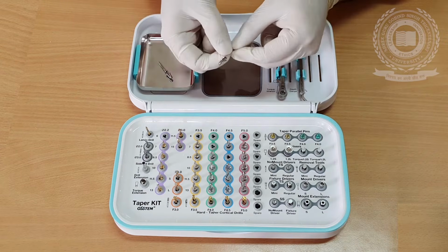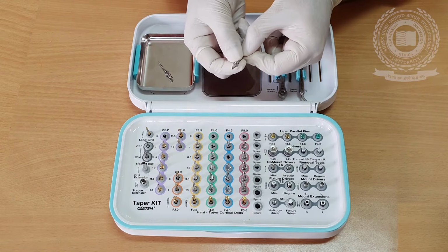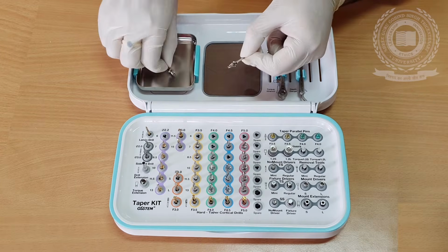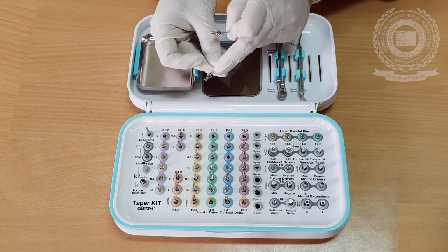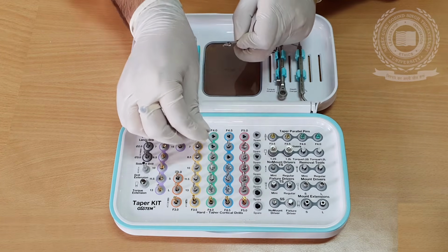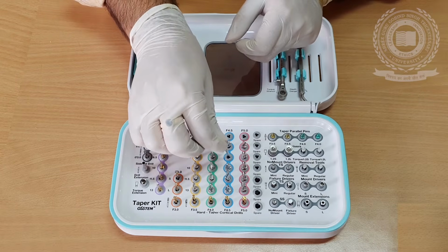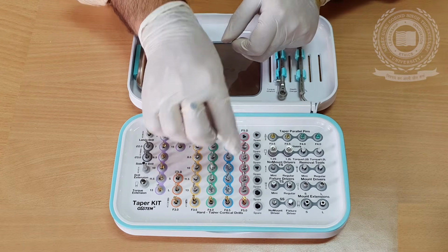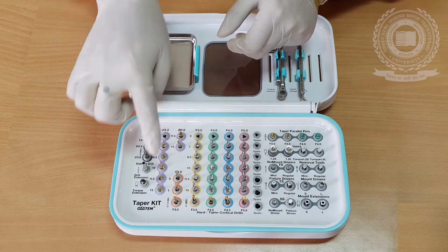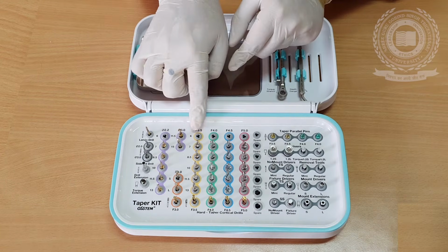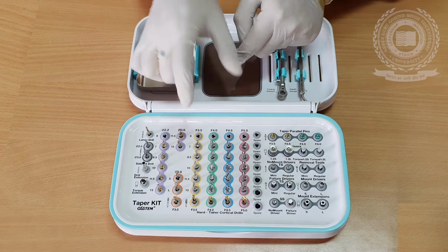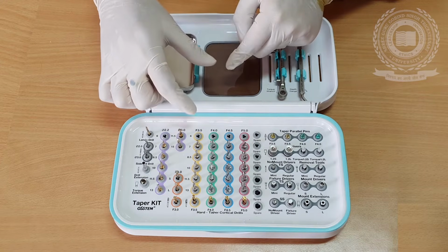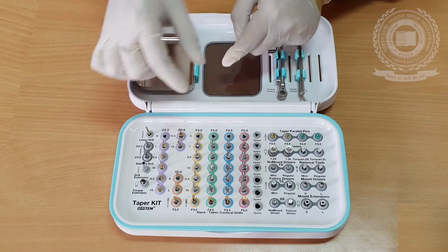Suppose if you find these drill like this, with holding this in hand, you can see, oh, it is blue, then it is 4.5. It is green, it means it is 4. Similarly, you can keep after surgery the right drill at right place. So they have provided color coding also. These color codings are also available on the packing of the implant, that I will show in my next video.